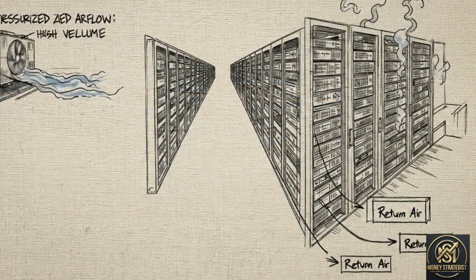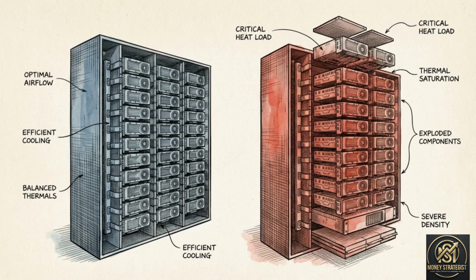We can trace this thermal crisis to a metric called thermal design power, or TDP. TDP is the maximum amount of heat generated by a computer chip that the cooling system is required to dissipate. NVIDIA's Hopper generation of chips maxed out at about 700 watts. The subsequent Blackwell architecture pushed that to 1,200 watts per individual chip. The next generation hardware, NVIDIA's Vera Rubin platform, shatters existing engineering standards. When 72 Rubin GPUs are clustered into a flagship rack-scale system, the total power density explodes, packing over 150 kilowatts of heat into the same physical footprint as the old 15-kilowatt enterprise rack.